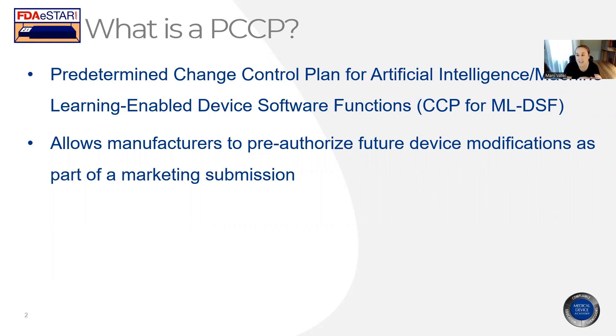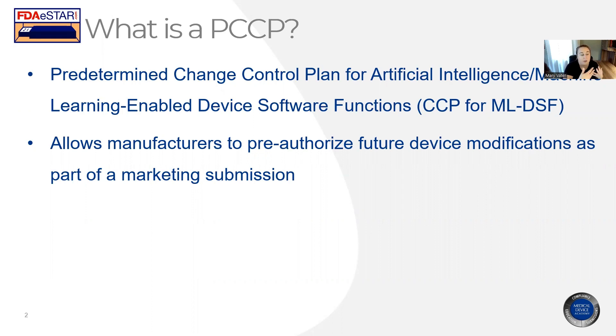It's abbreviated as PCCP or MLDSF. Basically, this is a plan that you can include in your marketing submission that will pre-authorize future device modifications that you intend to make to your device. So this would apply if you are submitting a 510K for a device that has an AI or ML algorithm as part of a software function, and you know you're going to be making certain changes. You can get those reviewed by the FDA without having completed the validations or having it implemented, and that will allow you permission to make those changes after you receive your authorization or clearance.